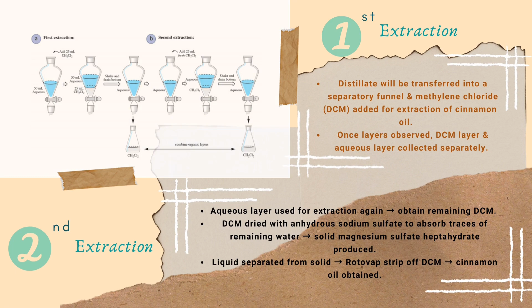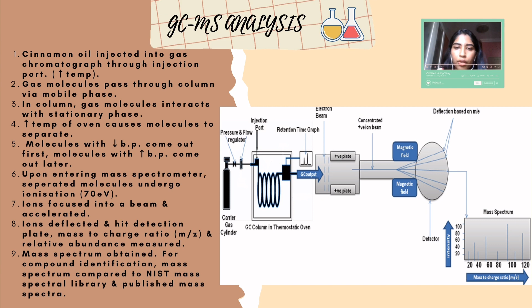For the analysis, we will start off by injecting the cinnamon oil into the gas chromatograph through an injection port at high temperature so that the sample will be volatilized and become vapor. Once volatilized, sample gas molecules will pass through a column via the carrier gas, which is also the mobile phase. The columns tend to be lined with stationary phase. The gas molecules being carried in the mobile phase will interact with the stationary phase. The high temperature of the oven will cause the molecules to separate as they travel through the column. The gas molecules with lower boiling point will come out from the column first. Meanwhile, the gas molecules with higher boiling point will come out from the column later, hence causing them to have different retention times.